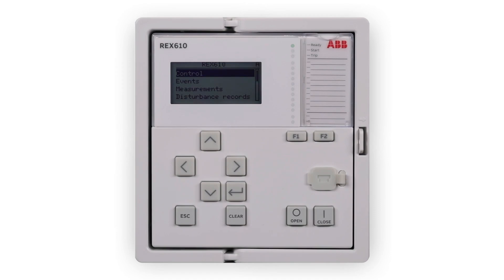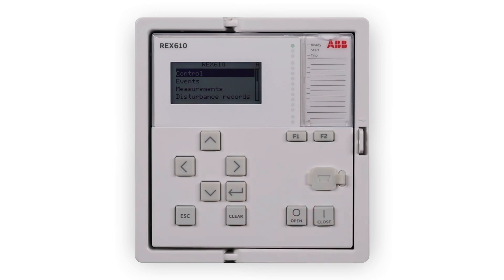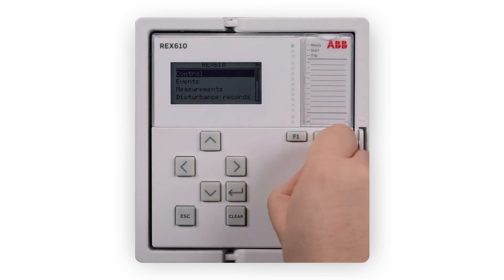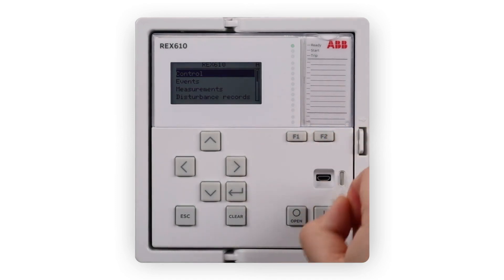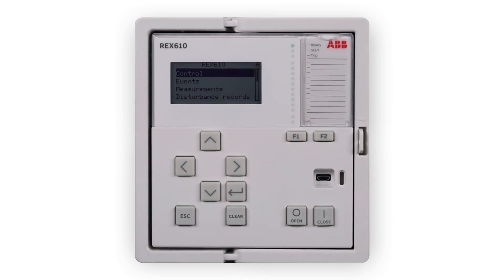REX610 has a micro USB Type-B front port that can be used as a communication port if auxiliary power is connected to the relay. If auxiliary power is not connected, the relay can be powered up from the USB. In this mode, the relay has limited functionality such as reading and writing configuration and settings.